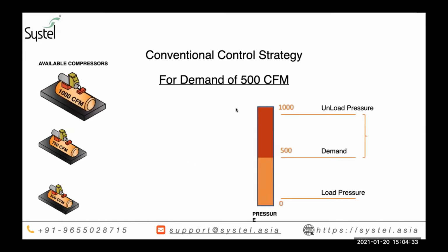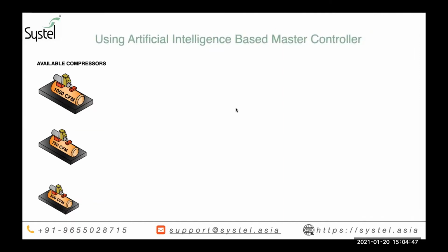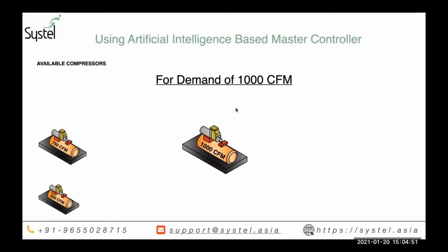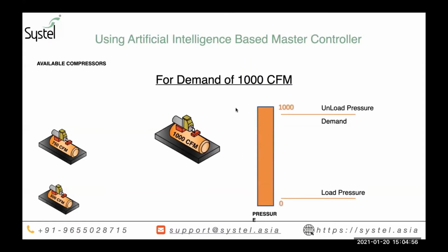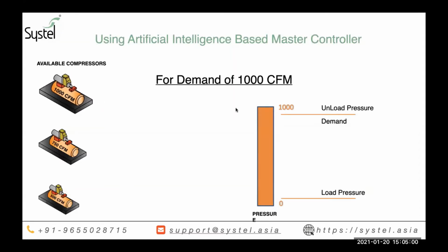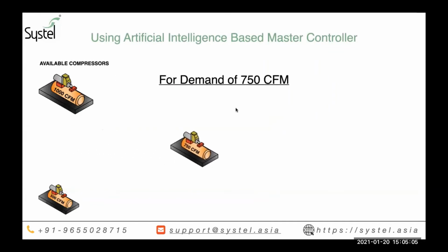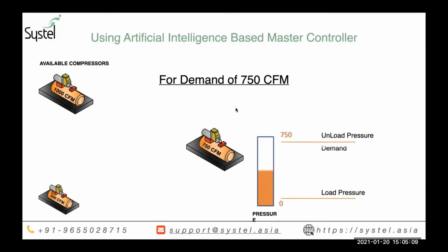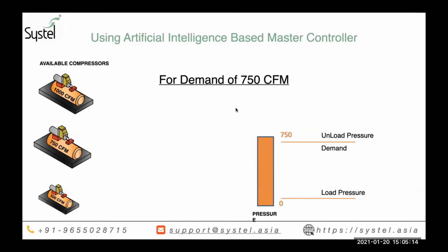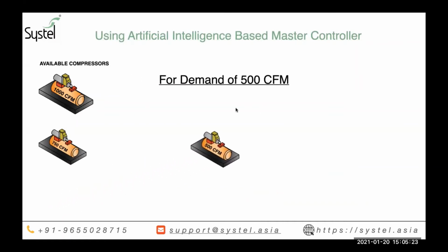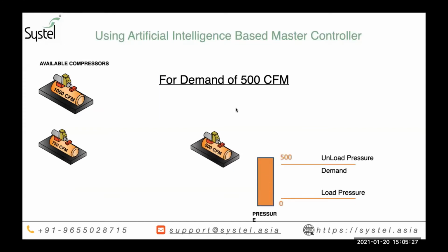There could be an option of bringing in a VFD compressor, but VFD compressors are most ideal only when they are operating at around 65 to 80% of their rated capacity. So with our artificial intelligence based master controllers, the controller can continuously evaluate the compressor's efficiency based on the power input and the flow output the compressor delivers. And to meet your demand, it can bring in the correct combination or correct capacity of compressor. So you always make sure that the compressors run at peak efficiency, and the wastage during compressor unloads is reduced to say less than 2%. This master controller can be integrated for compressor rooms with up to 32 or 34 compressors, or if you have multiple compressor rooms, they can also be integrated.